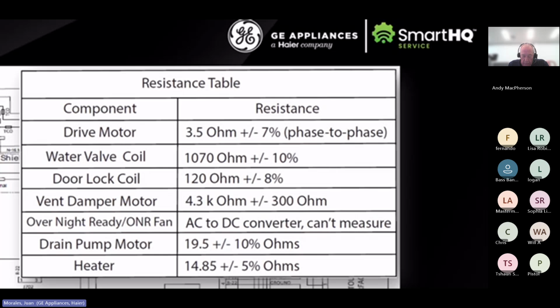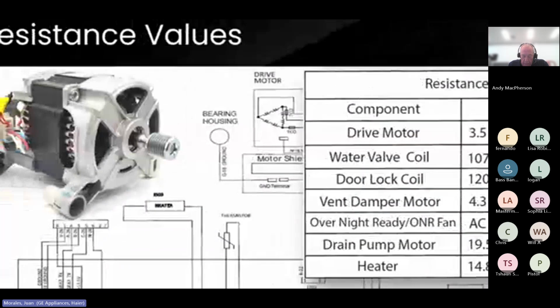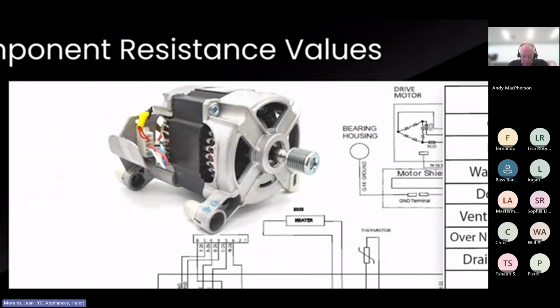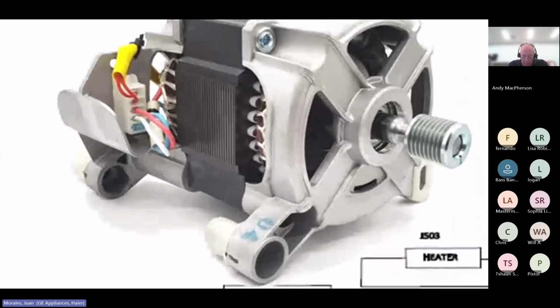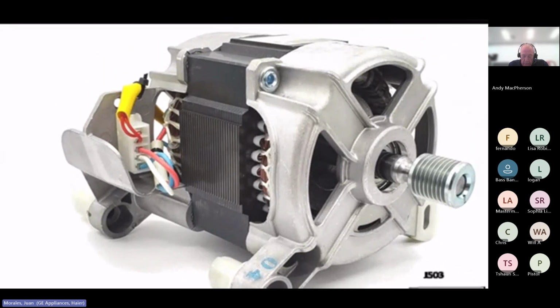Let's start with the motor. If I want to measure at the motor, if I can get to it, I would go between the red, white, and blue wires there and just measure any two combinations. According to this table, I should get about 3.5 ohms.